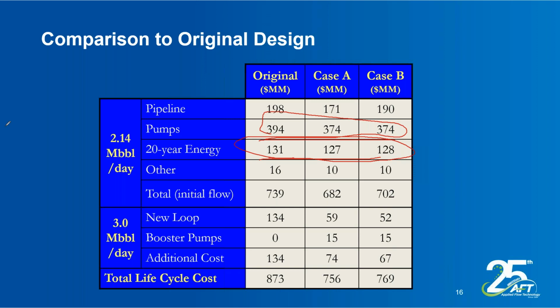Now, if you take a look at the design for 10 years down the road, this is the parallel flow path, and these are what the costs would be. And as you can see, there's significant amounts of savings by being able to use the automated sizing processes of what was AFT Mercury versus AFT Fathom ANS. And all it did was look at 3 diameters and a handful of different wall thicknesses. By only considering those things and making some assumptions of lots of commonality, it still saved $100 million on that project.